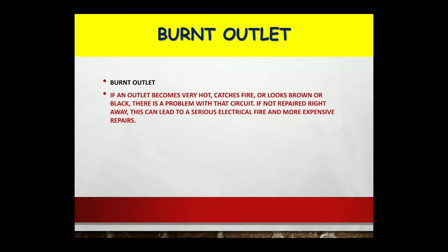So what do we have to do? Immediately turn off the circuit at the breaker box. Unplug everything from the outlet after the power to the outlet is off. Unless the outlet catches fire, you don't need to call any authorities for this type of emergency. Simply contact an electrician right away so that the repair can be made. So that is a very small type of emergency, the burnt outlet.